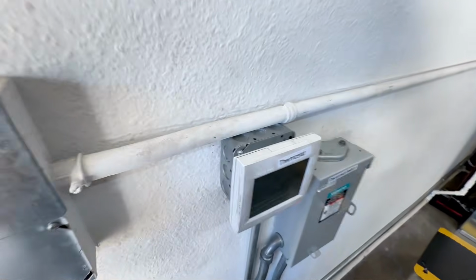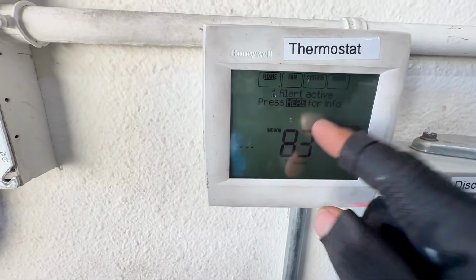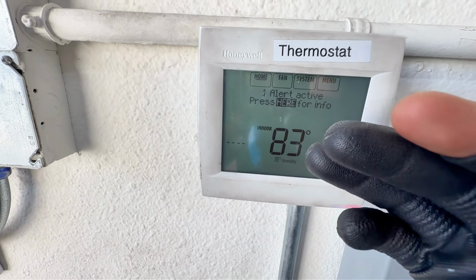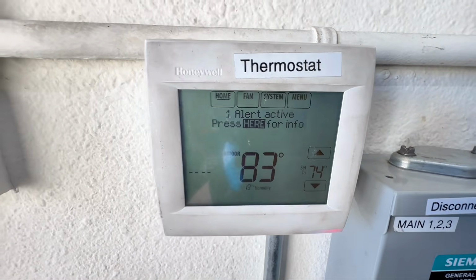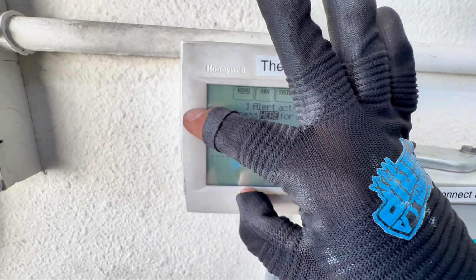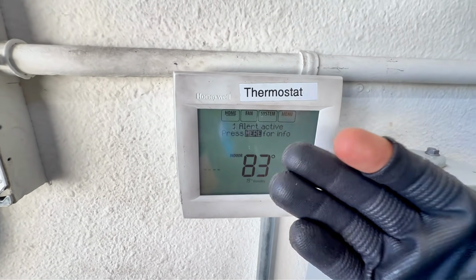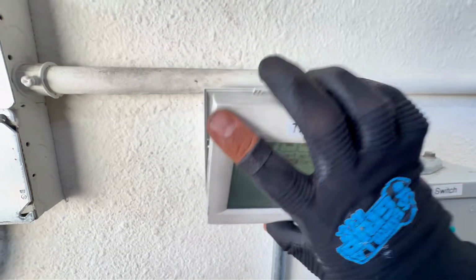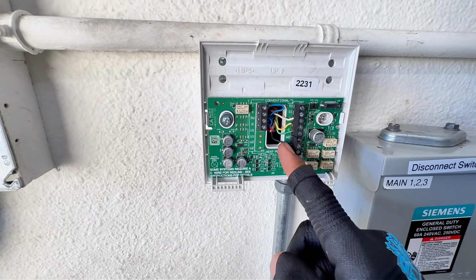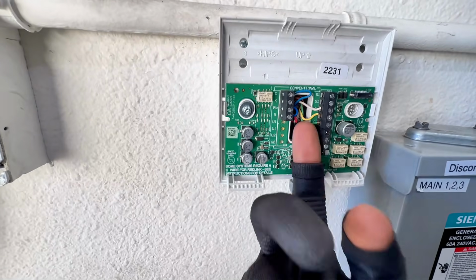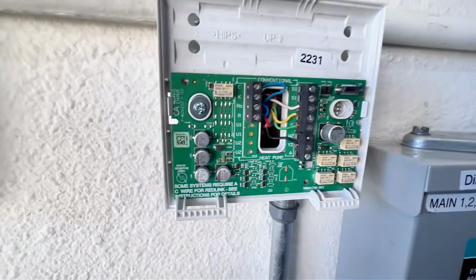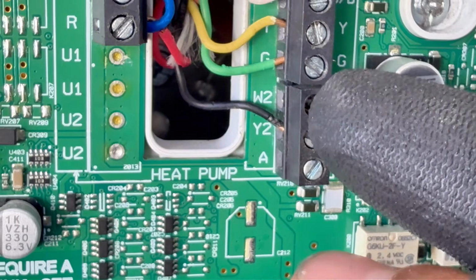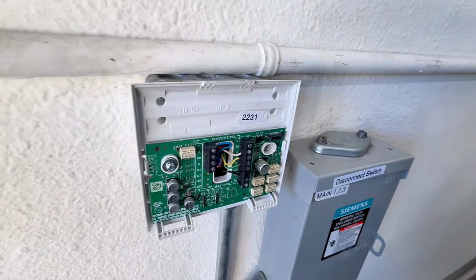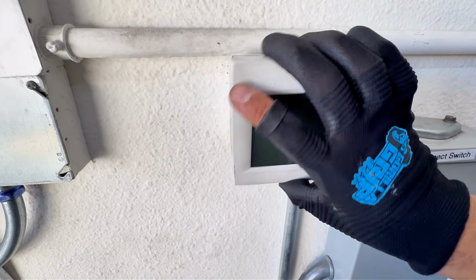But this will apply whether you're working on a stage 2 furnace or stage 2 cooling. So let's go ahead and go to the thermostat. Okay, so with this thermostat, you have to go to the installer options. Have in mind, there's going to be different ones; sometimes you have to push 2 buttons, you have to hold this one, and they're all going to be different. I already went through the manual. One thing first is make sure that you have the capability to do stage 2 and stage 1. For this specific one, if you can see right here, it's got the ability to do stage 2 cooling and stage 2 heating. So that's one. Your thermostat has to have the ability to do that. If it doesn't, then you can't do this. You have to get the right thermostat.